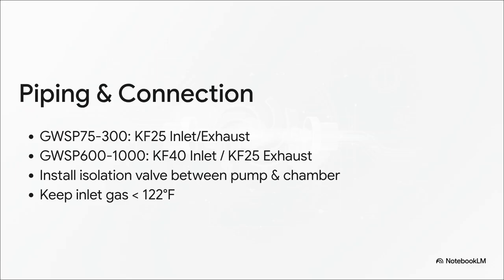Models up to the 300 use KF25 flanges for both inlet and exhaust, while the bigger 600 to 1000 models use a larger KF40 inlet to handle the higher flow. But here is absolutely the most critical point for installation. You have to install an isolation valve between the pump and the chamber. That stops any debris from blowing back into your clean chamber when you power down. Also, make sure your inlet gas stays below 122 degrees Fahrenheit. If it's running hotter than that, you're definitely going to need to add a chiller or a cold trap.